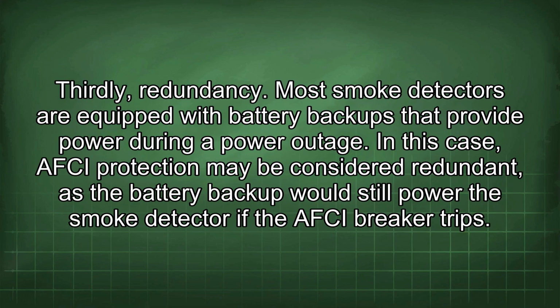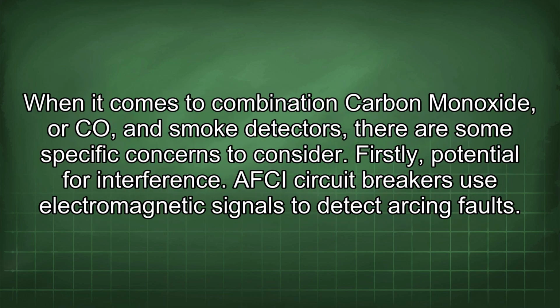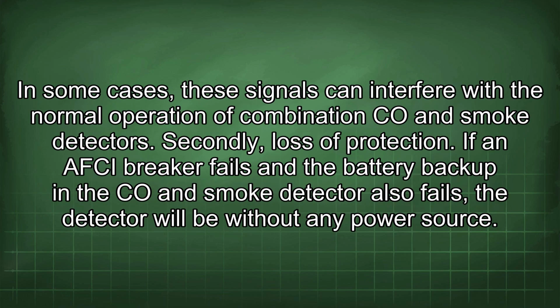Thirdly, redundancy. Most smoke detectors are equipped with battery backups that provide power during a power outage. In this case, AFCI protection may be considered redundant, as the battery backup would still power the smoke detector if the AFCI breaker trips. When it comes to combination carbon monoxide, or CO, and smoke detectors, there are some specific concerns to consider. Firstly, potential for interference. AFCI circuit breakers use electromagnetic signals to detect arcing faults. In some cases, these signals can interfere with the normal operation of combination CO and smoke detectors.